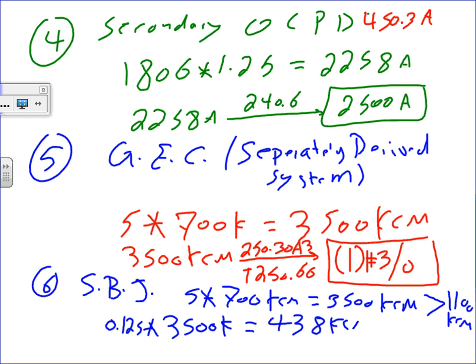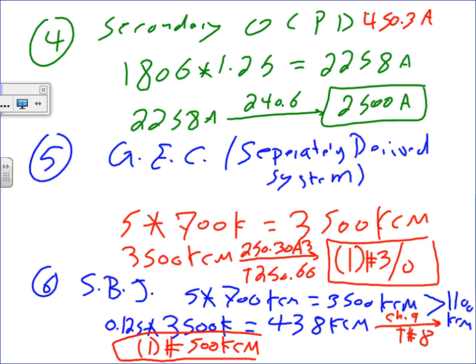438 kcm. And I don't know about you, Brad, but either you custom design yourself a cable this way, or where would you go? Anybody remember where we go? We go to Chapter 9, Table 8. If you go there, what's the next standard? 450? Do we have 450 or 500? 500, right? So how many conductors? One conductor. And what size? 500 kcm. And that would be my system bonding jumper that takes my ground to my neutral and bonds them together.